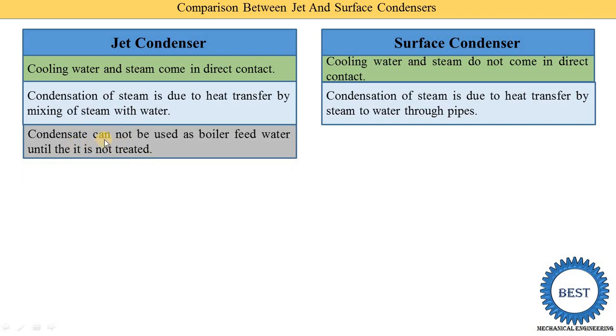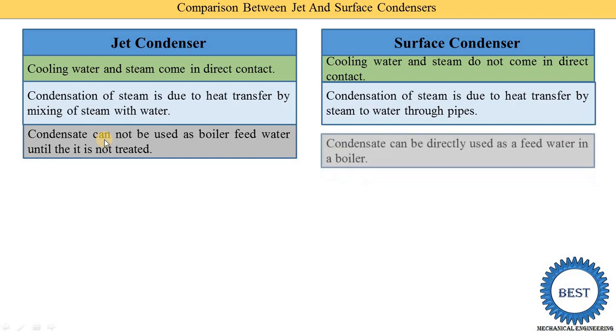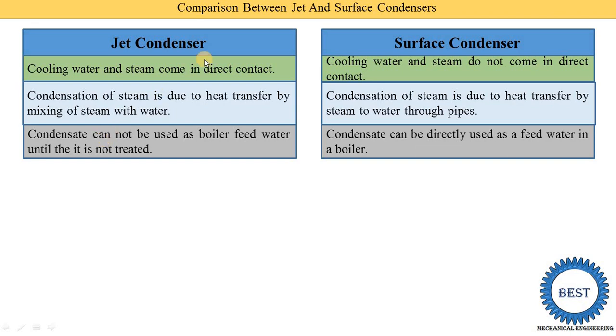Third point: in a jet condenser, the condensate cannot be used as boiler feed water until it has been treated — we need to treat the condensate before using it as feed water. In a surface condenser, the condensate can be directly used as feed water in a boiler; we can directly supply the condensate to the boiler using a pump.